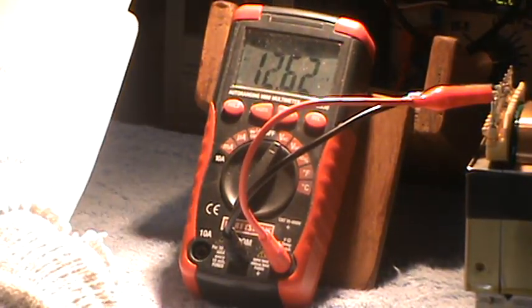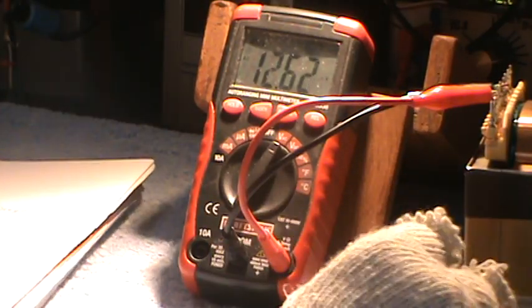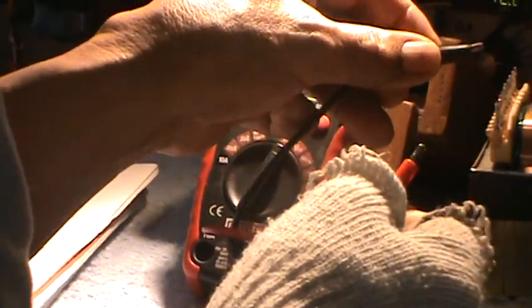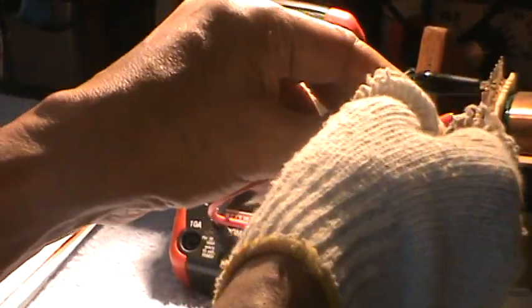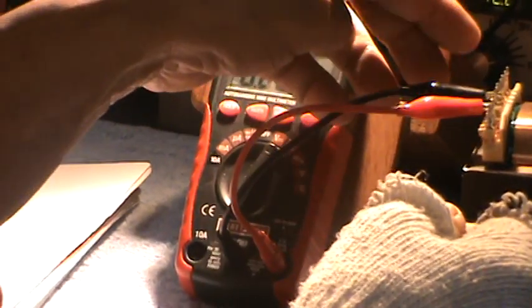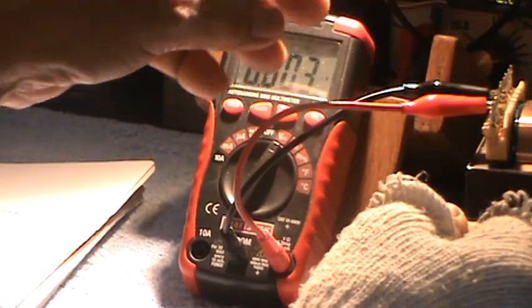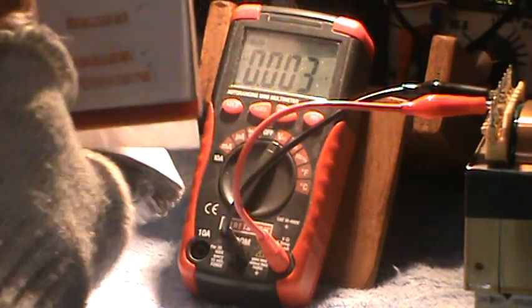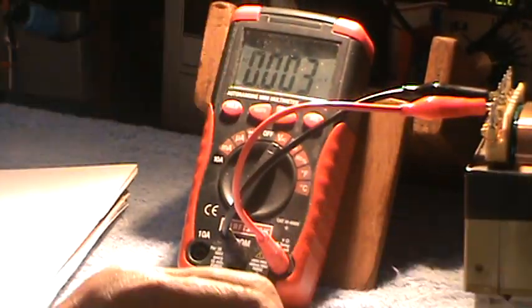Oh, what's next? 6 and 7. Okay, I will try to remove again this one. I will change terminals just to be safe. 6 and 7. 1, 2, 3, 4, 5, 6. This is number 6. And 7. 1, 2, 3, 4, 5, 6, 7. Yeah. Because across terminals 6 and 7, a while ago, I measured the resistance of 1.4 ohms. And supposed to be, we could measure an AC voltage across it.